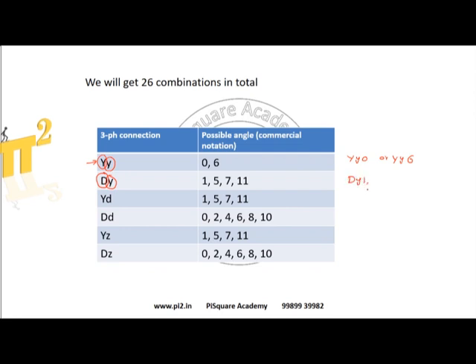DY1 — DY1 means the high voltage winding is at 12 o'clock, and the low voltage winding is at position 1, which means the low voltage winding is lagging the high voltage by 30 degrees. Now we will see how to identify this number, which is very crucial. Be more attentive now.